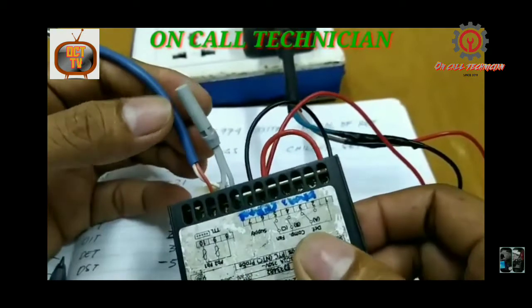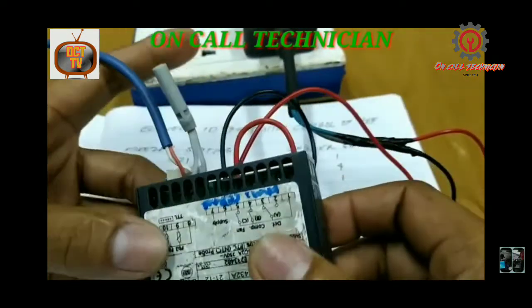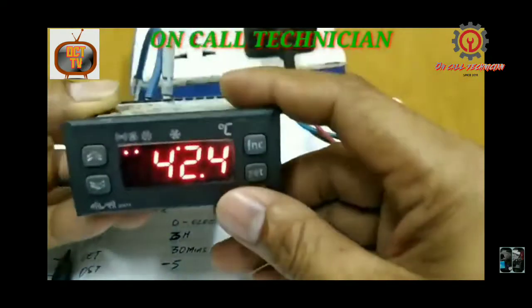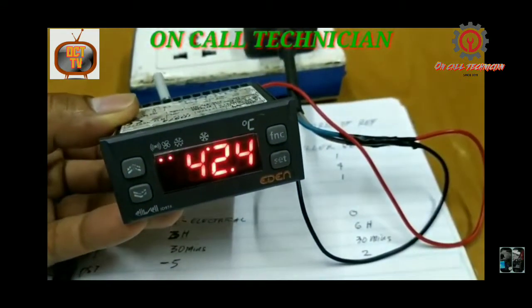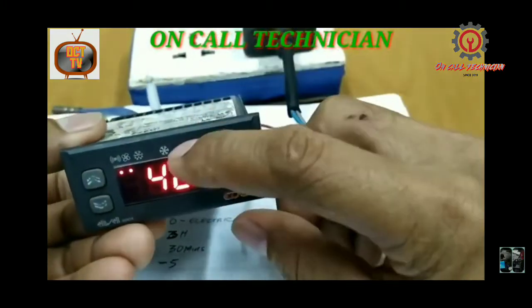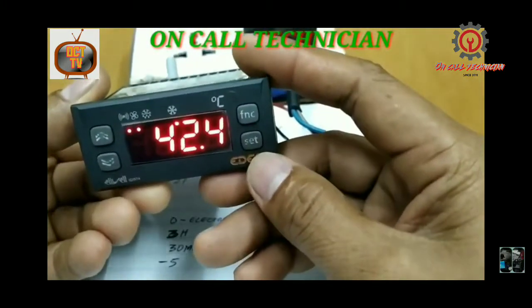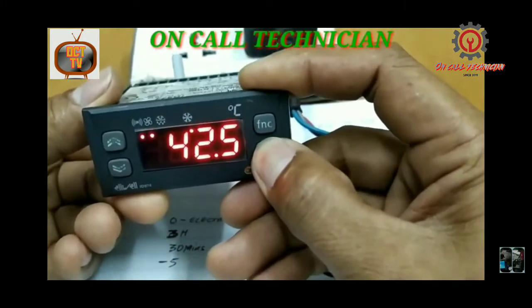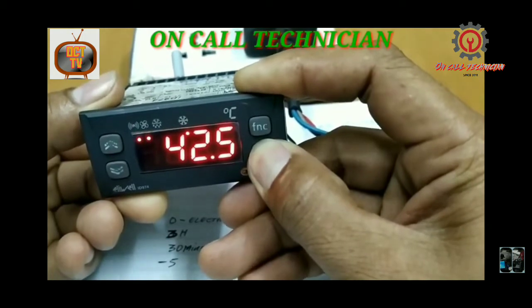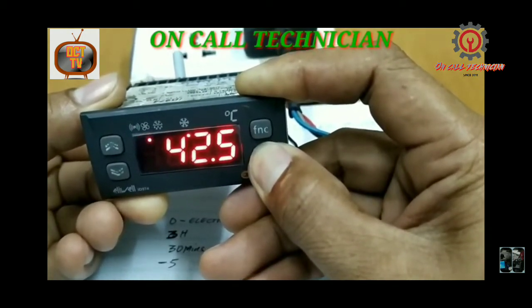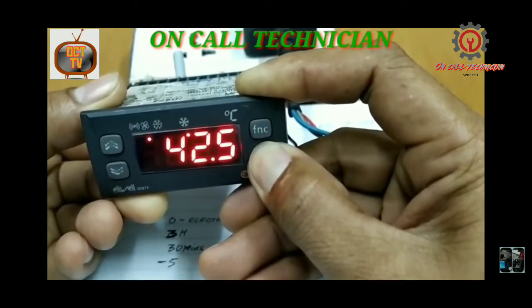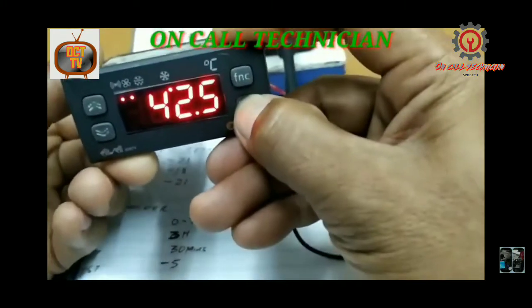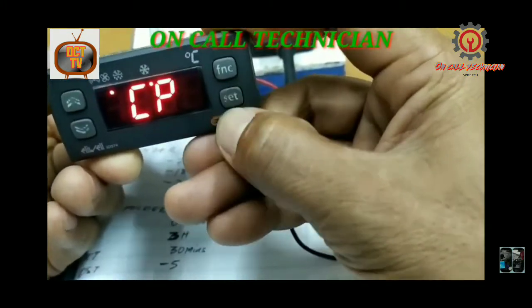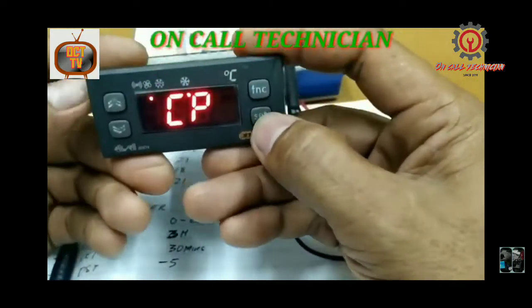Let's start. This is the room and the evaporator sensor. As you notice, they are not the same, but in reading they are the same. Right now we have 42 degrees Celsius, that's my room temperature here in my salon. To enter the parameters, guys, just press the set button and we enter the programming mode. Let's do it again. CP appears, which means we are now in the programming mode.